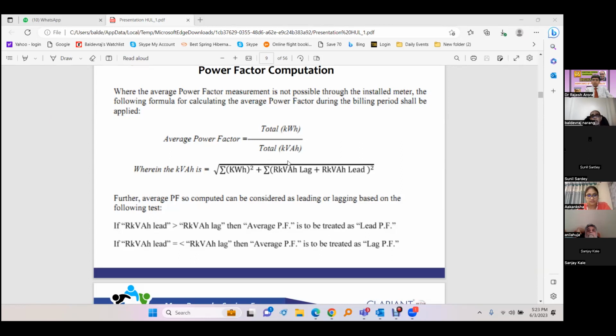And earlier there was a very big issue. People were using capacitors indiscriminately. They were using capacitors without any requirement just to get the full incentive. And everybody used to get full incentive, like 7% incentive was available in Maharashtra. Even if they needed, say, 1000 kVAR, they were using maybe another 500 or 1000 even, or any amount, without knowing what they were doing. They did not want to lose the incentive. So later on, this became a problem, and unnecessary reactive power, capacitive power, was being exported to the grid. And that creates problems under low load conditions, and there were over-voltage problems.